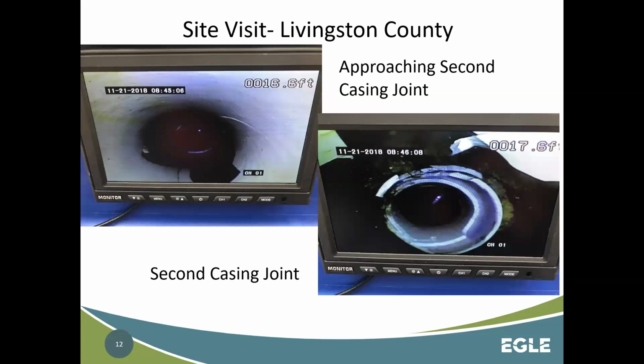All right, we're going to move on to our next one here. There's a homeowner whose well had been struck by lightning, and the pump had stopped working completely. The contractor went out and replaced the pump. Once the pump was in place, there was all kinds of cloudy water and grit. When we talked to the contractor at the time, they knew that most likely the lightning strike had destroyed or done some damage to the plastic casing, but they weren't sure how much and at what depth it had occurred.